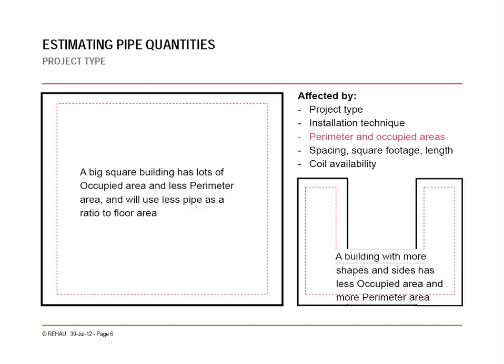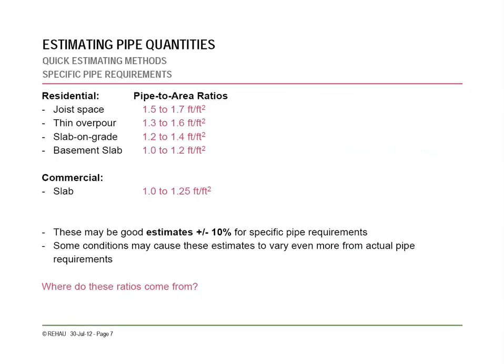One thing to note here is that you usually want to be running a tighter spacing between your tubes at the perimeter of a building versus a general occupied area in the middle. As we'll show here, REHAU will have you calculate the areas separately, but in general, all you want to do is just slightly overrate your square footage area to make a quicker calculation.